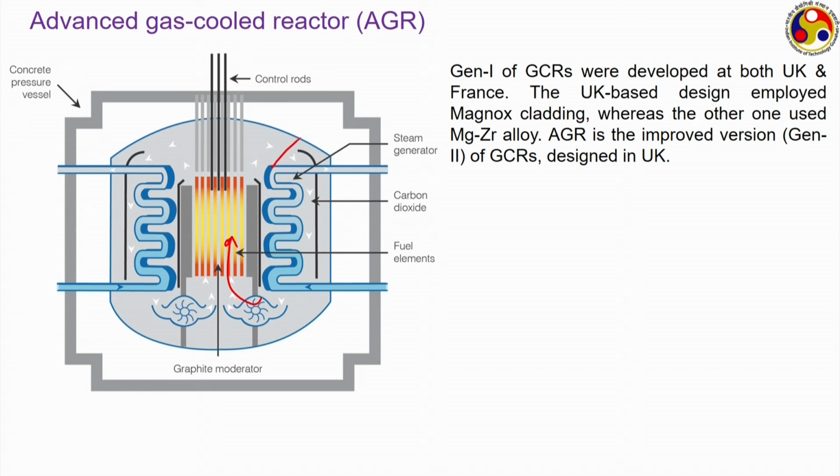Inside these generating tubes we have water which is coming from some external source, and inside the steam generation plant that water is getting converted to vapor. This is where the water is entering, and here it is going out as a mixture of steam and water. The same is true for this side as well.